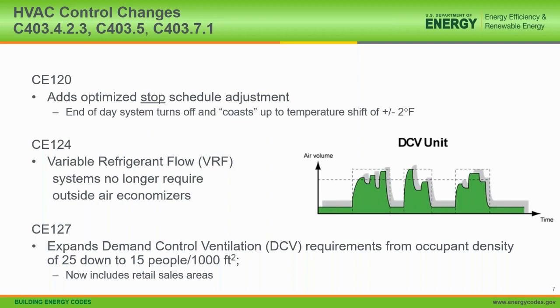CE 127 expands demand-controlled ventilation requirements from an occupancy density of 25 down to 15 people per 1,000 square feet. Basically, if you look at the IMC ventilation tables, what that means is pretty much retail sales area is the only new area. Before, we covered classrooms, conference rooms, and lecture halls with demand-controlled ventilation. Now we're also going to be including those large retail sales areas, which have a pretty high ventilation requirement due to the large number of people that might be there on the big Thanksgiving sales day, but they spend a lot of time almost empty at other times. So this does adjust that ventilation to be appropriate for who's actually in the building.